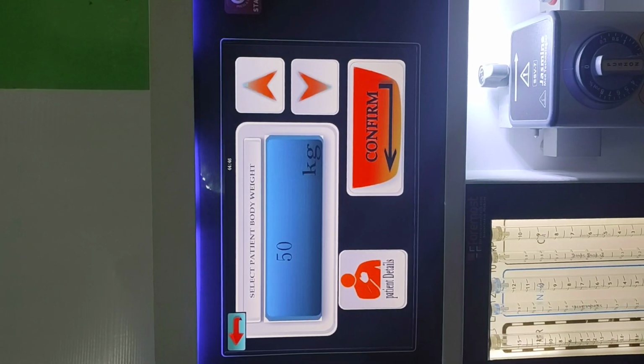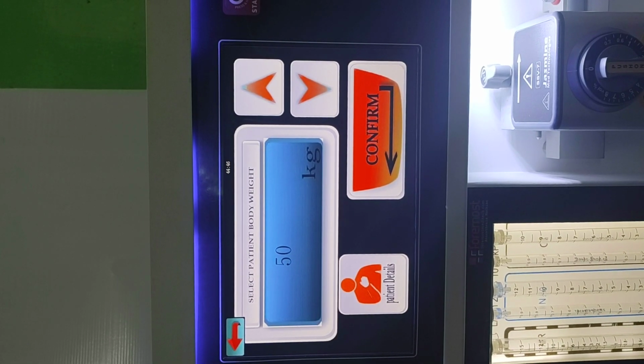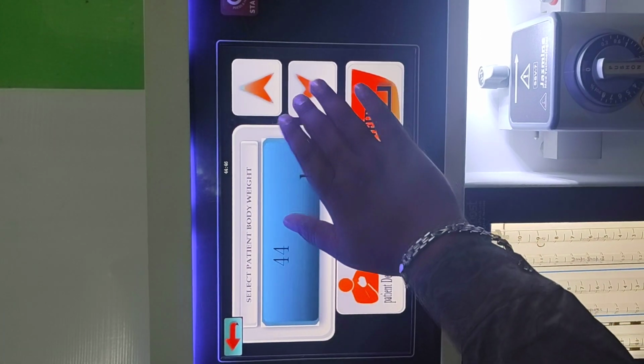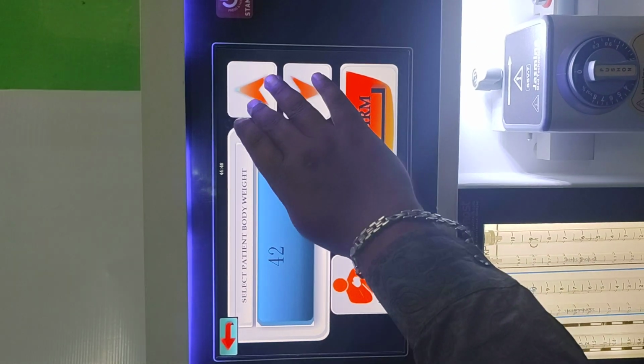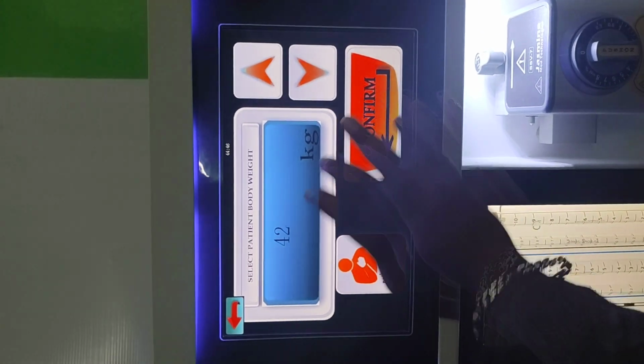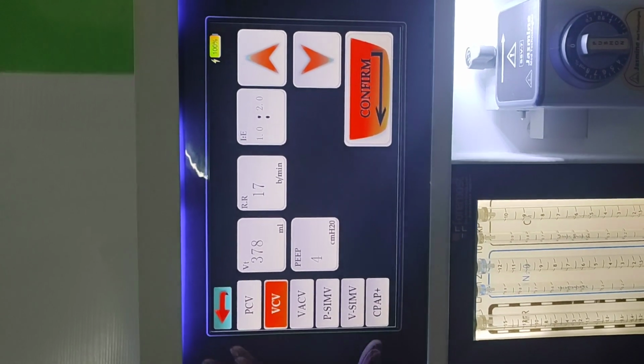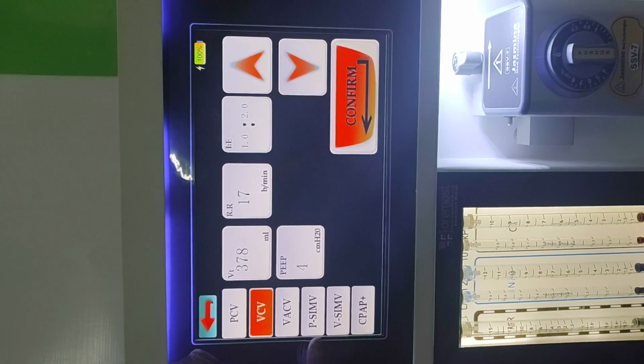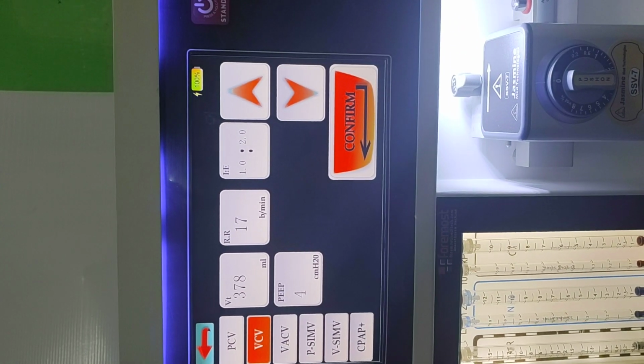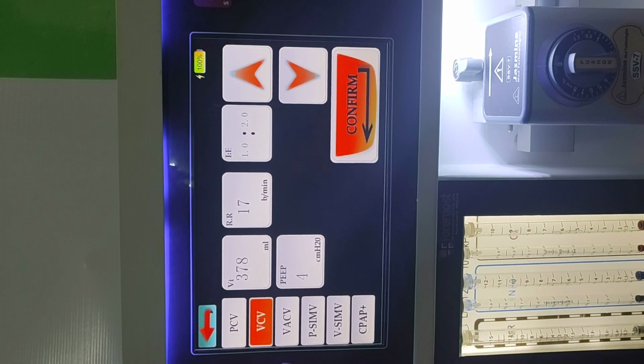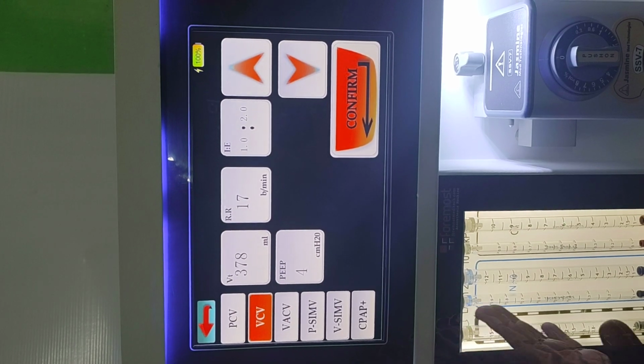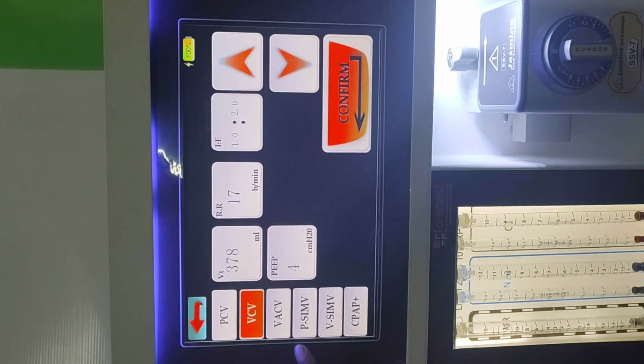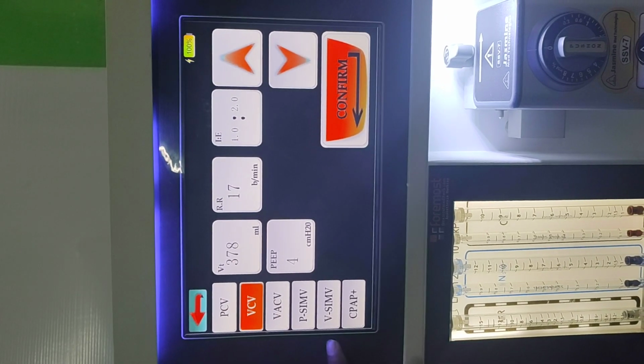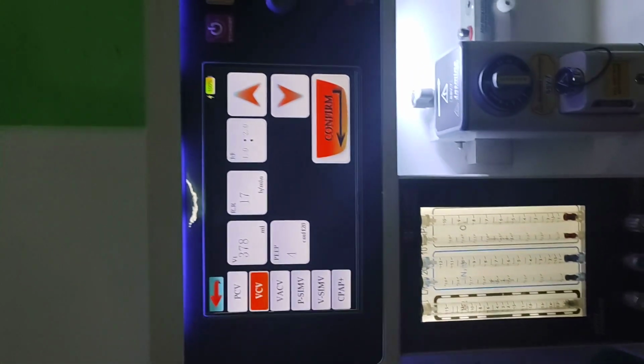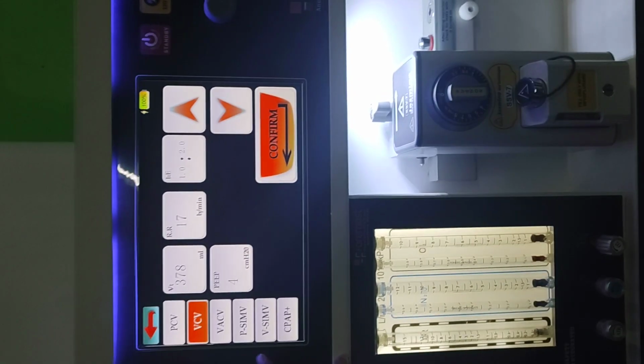If you select male, then you can put in the body weight, which is the ideal body weight as per the patient height. Let's say it's 42 kg, confirm. Now these are your modes. You have pressure control ventilation and volume control ventilation, which are mandatory modes. Then you have assist volume control ventilation, which is volume control with patient triggering, and you have SIMV pressure or SIMV volume control, where you are controlling either pressure or volume.